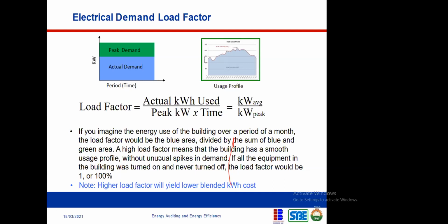Now, the problem is that if you're using 10%, you have to recover the depreciation for 20 capacity. You're not recovering the depreciation for 10 capacity. Okay, so it's going to impact your unit cost of electricity. And again, if you're burning fuel at 10 kVA, you're not going to achieve the optimum value from the petrol you're burning, because that generator is designed to burn more fuel, so you're not going to achieve the best fuel efficiency at that level. All of this will impact the electricity output you get from that system. That's what that caveat is talking about. When you have a higher load factor, you're going to have a lower cost of electricity production.